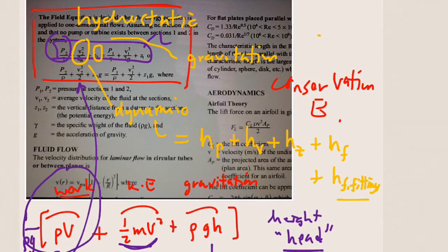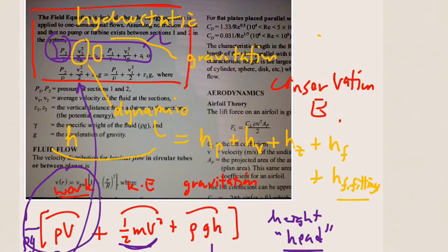So, we're going to say that the energy that you start out with, or the effective H effective from the initial situation before going through all these pipes, it will be equal to this new situation. So, these different pressure heads expressed in terms of the hydrostatic pressure, the dynamic pressure, the gravitational head, and then the frictional loss, and then the loss of the fittings.